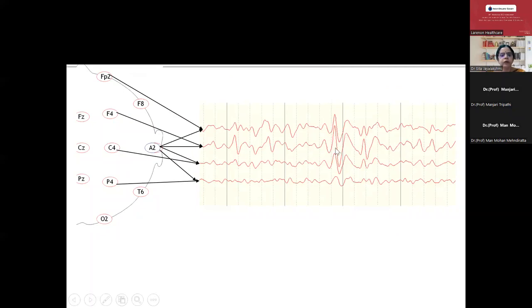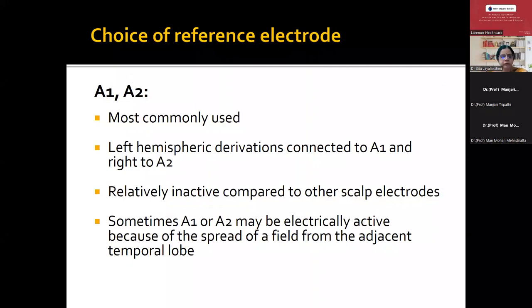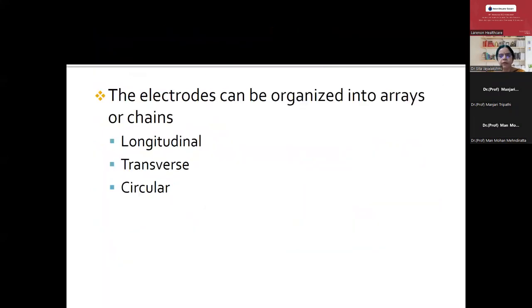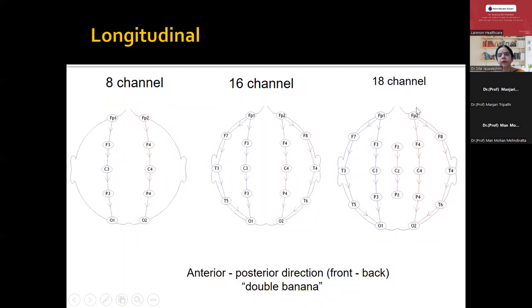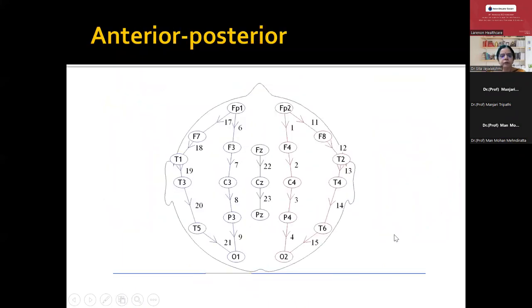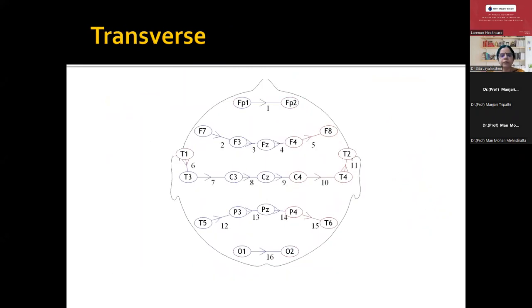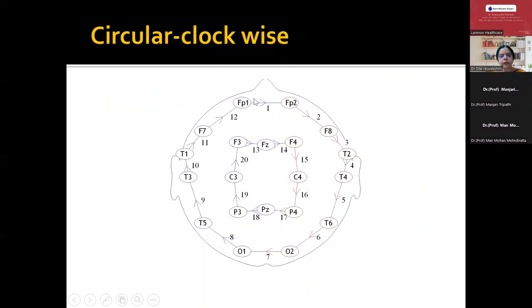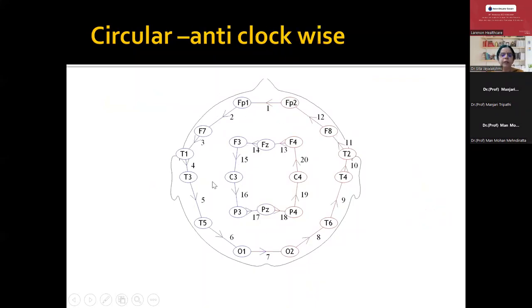If here the maximum is showing at F4 — all connected to A2 — then the choice of reference electrode is either A1 or A2 mostly. But we avoid this in temporal lobe epilepsies and we avoid CZ in sleep-related epilepsies. These electrodes can be organized into longitudinal, transverse, or circular montages. The double banana montage — the longitudinal montage — is where they are connected longitudinally. We also have the transverse montage, where you connect all electrodes transversely. Circular montage can be clockwise or anticlockwise. All these are now programmed within the machines — the moment you go to that montage, the EEG automatically changes.